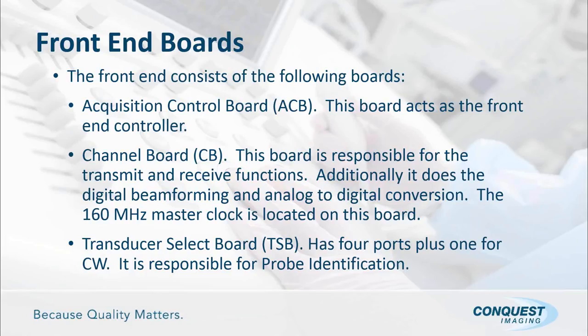The other main function of the acquisition control board is that it's the path of communication to what we call the back end, where all the scan conversion is done. All the information that the front end acquires gets passed to the back end for further manipulation. So that's the acquisition control board. We also have the channel board. It's a single board, responsible for transmit and receive functions. The Epiq 5 and 7 are a 128 channel system.